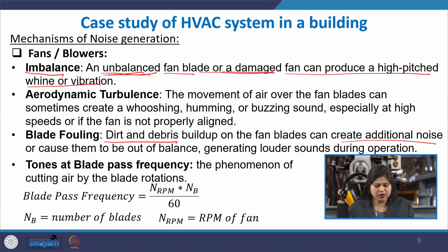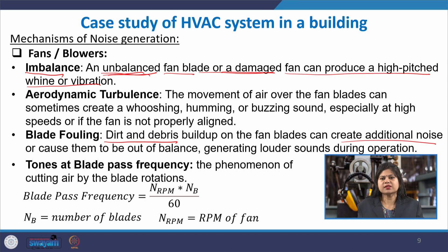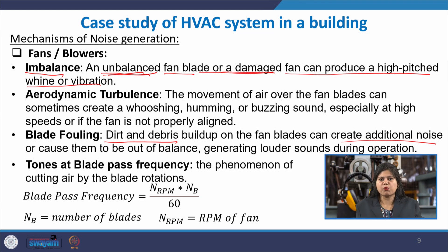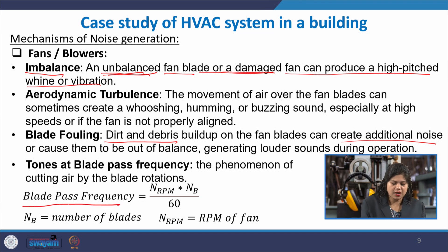Then there is blade pass frequency — a tonal noise. This noise is created because as the fan rotates, the blades cut the air around it. This blade rotation and air-cutting phenomenon creates noise corresponding to the rate at which air is cut by the blades, given by the blade pass frequency formula: number of revolutions per second multiplied by the number of blades.